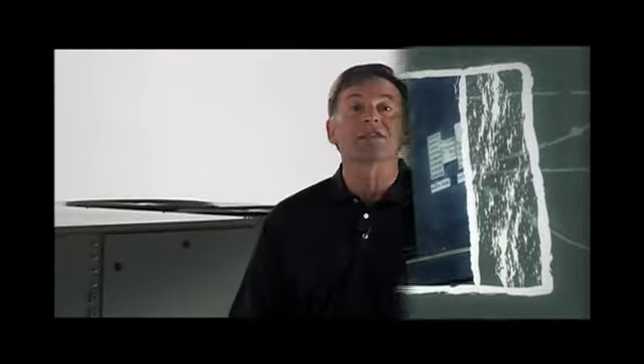The sheet metal cabinet uses nothing less than 18-gauge material for structural components with an underlying coat of G90 galvanized. To ensure the leak-proof integrity of these units, the design utilizes a one-piece top with a 1/8-inch drip lip, gasket-protected panels, and screws. Every package unit uses the toughest finish in the industry, using electrodeposition baked-on enamel tested to withstand a rigorous 1,000-hour salt spray test per ASTM B117.